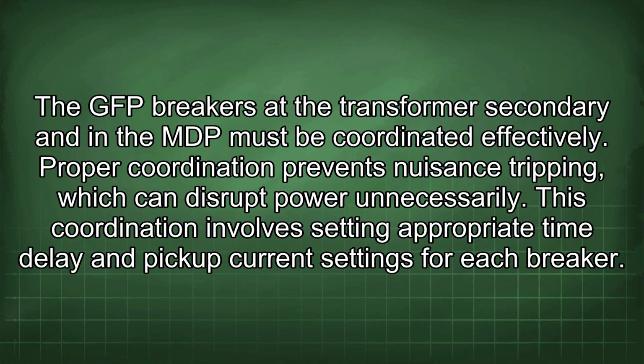The GFP breakers at the transformer secondary and in the MDP must be coordinated effectively. Proper coordination prevents nuisance tripping, which can disrupt power unnecessarily. This coordination involves setting appropriate time delay and pickup current settings for each breaker.